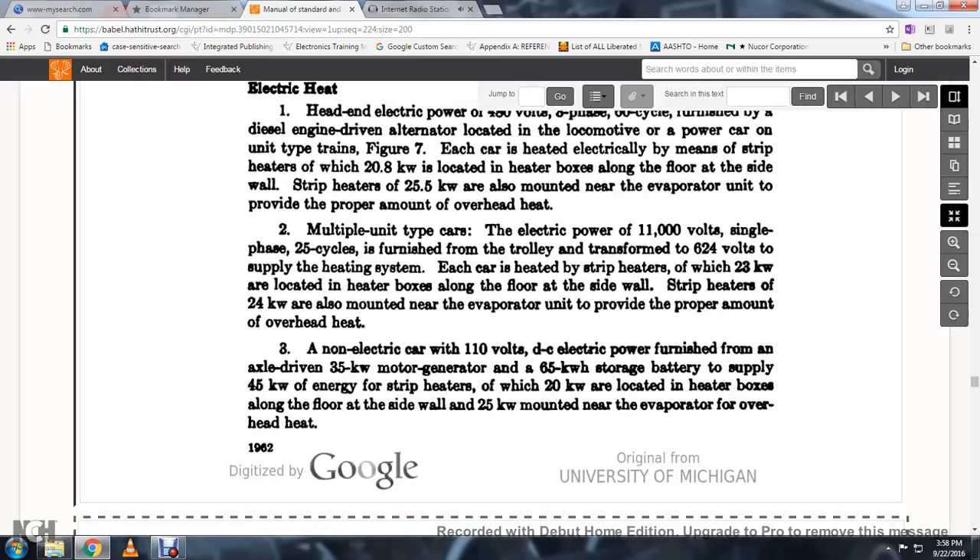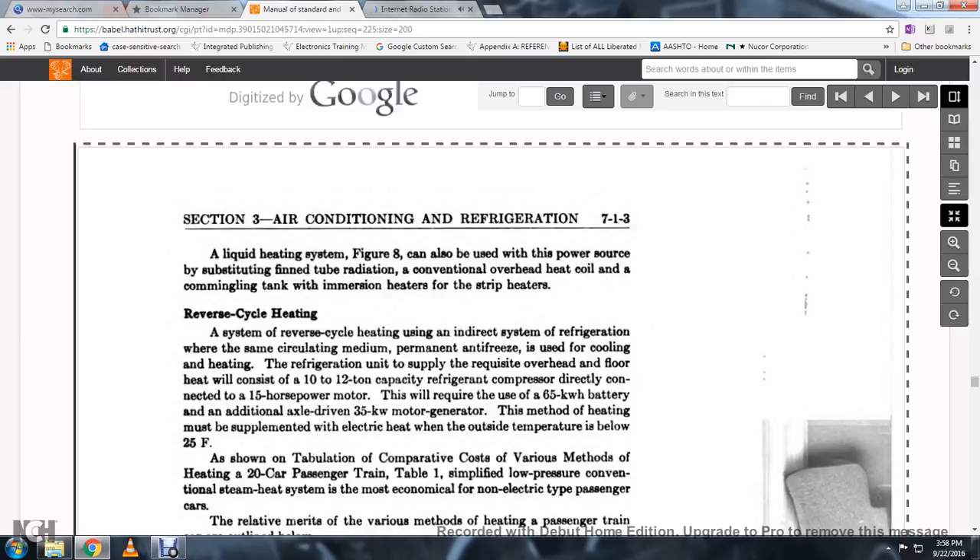For the non-electrical car, 110-volt DC electrical power is furnished from an axle-driven 35-kilowatt motor generator with a 65-kilowatt-hour storage battery to supply 45-kilowatt energy. Strip heaters of 20 kilowatts are located in the heater box along the floor and side wall, with 25 kilowatts mounted at the evaporator for overhead heat. A liquid heating system, Figure 8, can also be used, substituting tube radiation and conventional overhead heat coils with immersion heaters and strip heaters.